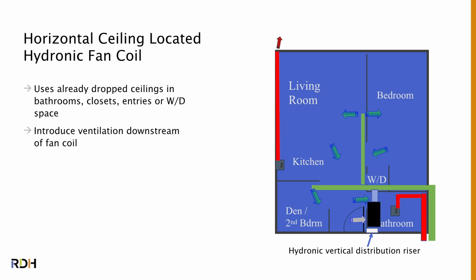So here's an idea of what it would look like. The black here would be the fan coil. There's my ventilation. We introduce the ventilation after the fan coil, so I don't have to run the fan coil to deliver ventilation in the space, right? And save some energy, turn the fan off when it's not needed. And we can distribute that heating and cooling throughout the space with something that looks like that.